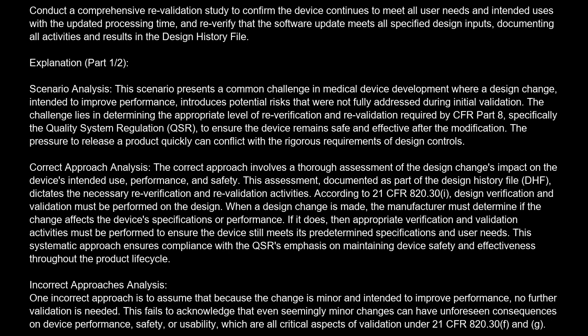When a design change is made, the manufacturer must determine if the change affects the device's specifications or performance. If it does, then appropriate verification and validation activities must be performed to ensure the device still meets its predetermined specifications and user needs. This systematic approach ensures compliance with the QSR's emphasis on maintaining device safety and effectiveness throughout the product lifecycle.